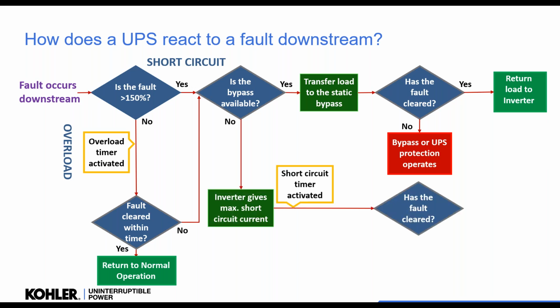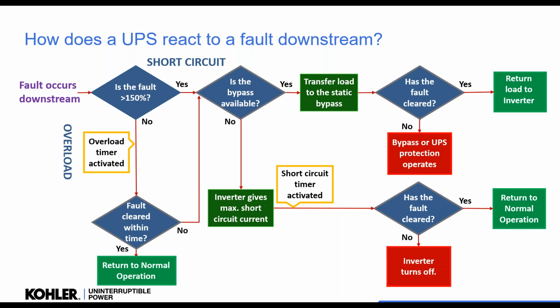Now, if that bypass isn't available, this is where the inverter goes into a short circuit current limit, and it will put out its maximum, maybe 2 times or 3 times the nominal current. So it's quite low, for very little time. And it will use that to try and clear the fault. If it does, it's great. The inverter comes out of current limit, everything goes back to normal. If not, typically the inverter will turn off at some point, and different manufacturers do it differently.